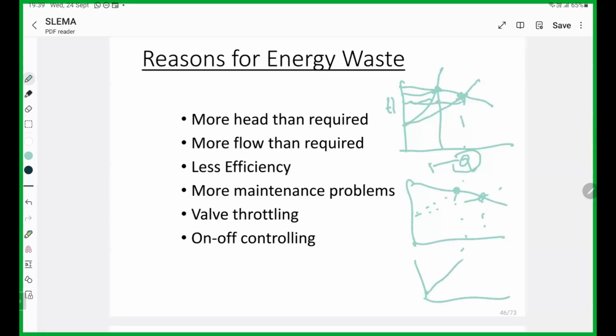This efficiency curve is something like this, with the best efficiency point. If the head is more than required, then the efficiency is less. The reason is that the pump is not properly selected, and they didn't consider the specific speed. Then definitely you get a less efficient pump. There is also a maintenance problem, and valve throttling or on-off control. This one is also important.